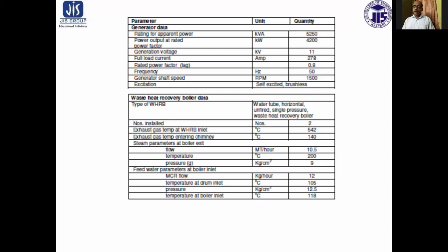The other generator data: rating for apparent power is 5250 kilovolt-ampere, which is 4200 kilowatt power output at rated power factor. Generation voltage is 11 kilovolt. Full load current is 278 ampere. Rated power factor 0.8. Frequency 50. Generator shaft speed 1500 rpm. Excitation is self-excited brushless.